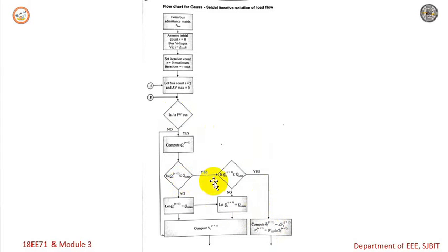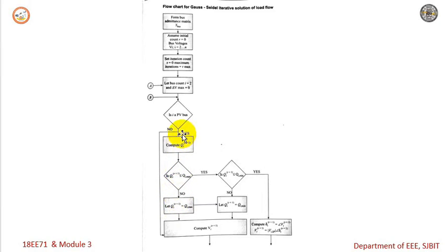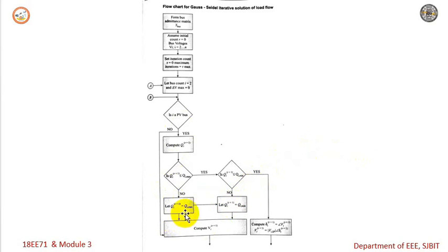If the calculated reactive power goes beyond the minimum or maximum limits, then we treat that particular bus as a PQ bus and compute the voltage V_i. If the calculated Q exceeds the maximum value, set Q equal to Q_i max. If it is less than the minimum value, set Q equal to Q_i min. Under both conditions, treat the bus as a PQ bus and compute V_i.